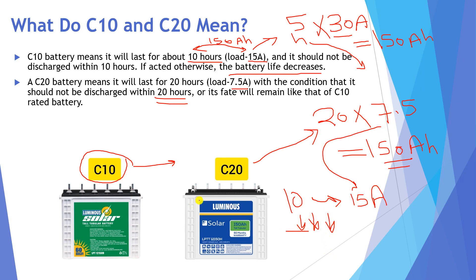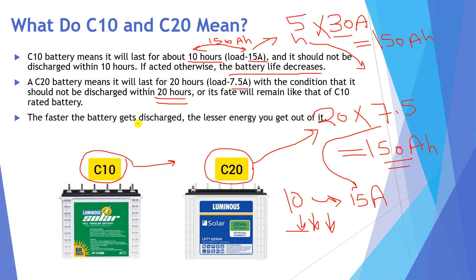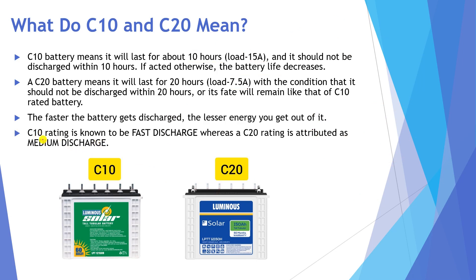According to the application, you choose C10, C20, C5, C100, and so on. Remember that the faster the battery discharges, the less energy you will get out of it. C10 takes only 10 hours so it is known as fast discharge. C20 is considered medium discharge — it takes 20 hours, which is a longer time than C10.